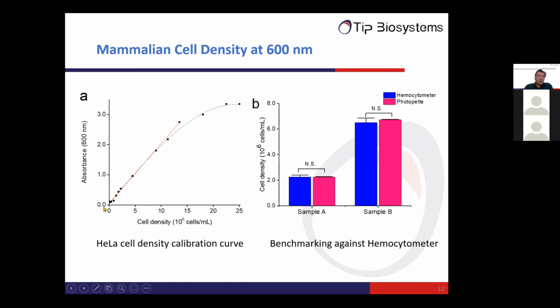And you see this is what you expect: at lower absorbance, lower cell density, you have an absolute linear correlation. And later you have a little bit of flattening of this curve. But please recognize here, we already have absorbance values of 3, which is very, very high. The advantage is that without having to dilute your samples with a Photopette, you can measure very high cell densities. Most instruments can measure probably about 2.5. If I say this, it sounds like quite a small difference, 2.5 to 3, but actually it's a very big difference, because remember, this is not a linear scale. The absorbance is a logarithmic scale of the light absorbance.